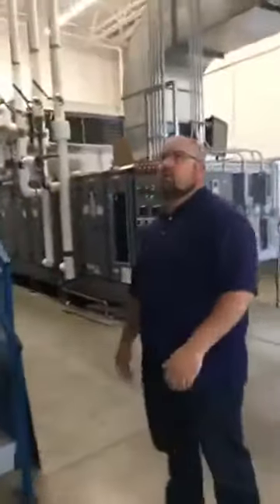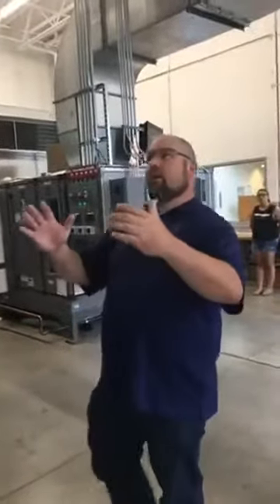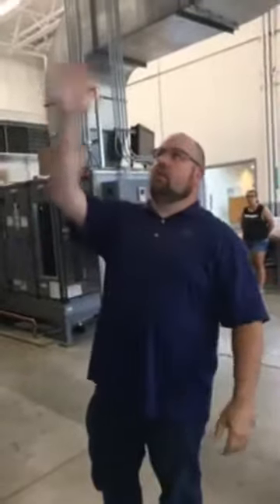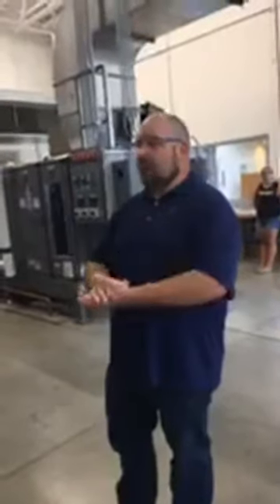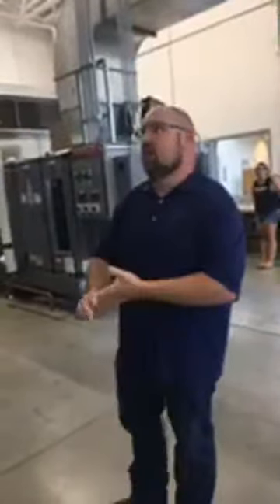So one thing Paul was alluding to that I think we want to clarify here is we're really demonstrating two separate systems within one. So on the right we have fan number 2, on the left, my left, fan number 1. That's going to give us the ability to demonstrate two independent HVAC systems, one with a functioning fire life safety system and one that has failed or not been installed or installed incorrectly, not maintained, something of that nature. So for demonstration purposes, we'll talk about system 1 versus system 2.